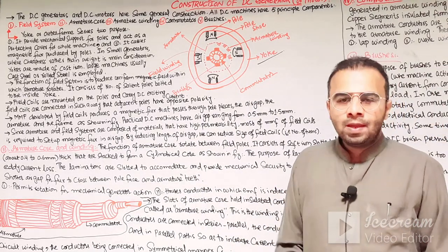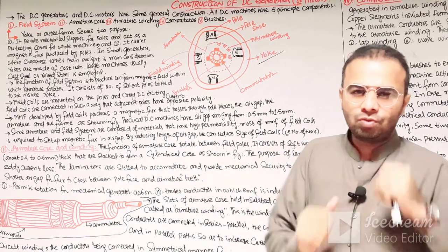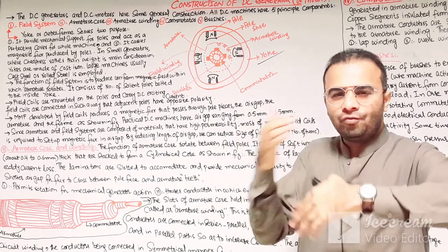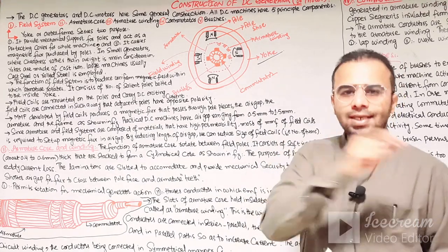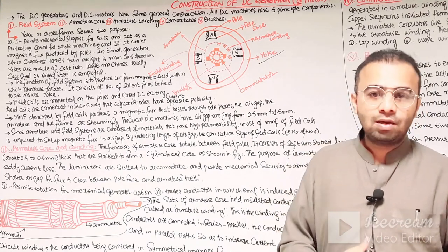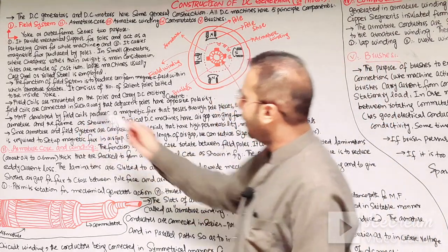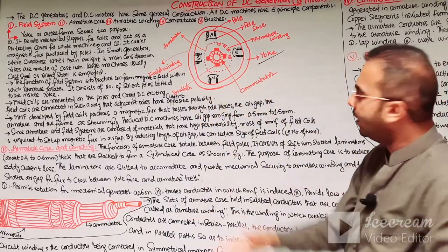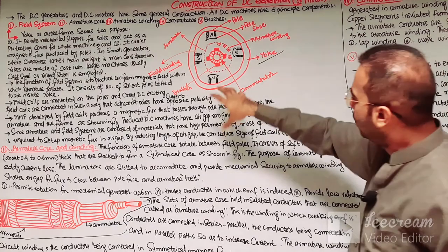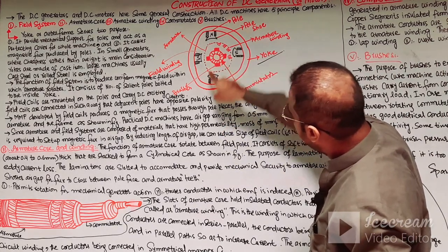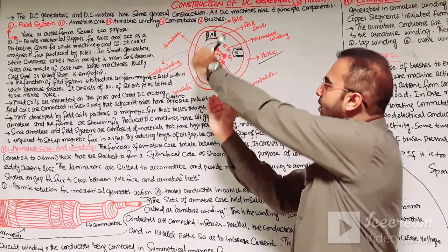In the case of a separately excited DC generator, the field coils are excited by an external DC source and the armature is rotated by a prime mover. The rate of change of flux linkage d-phi/dt induces an EMF in the coil according to Faraday's law of electromagnetic induction. The field coils are mounted on the poles, carry DC exciting current, and are connected such that adjacent poles have opposite polarity.